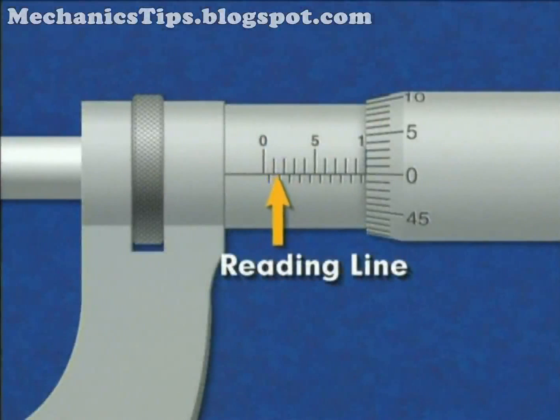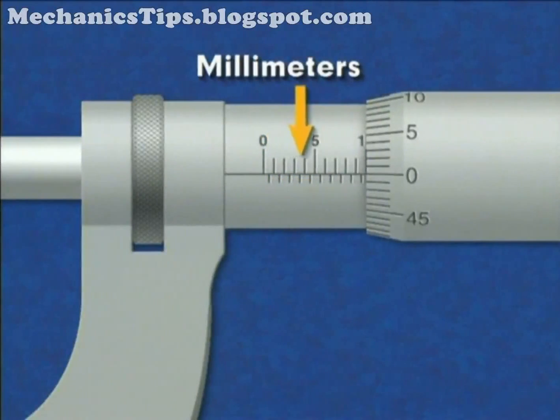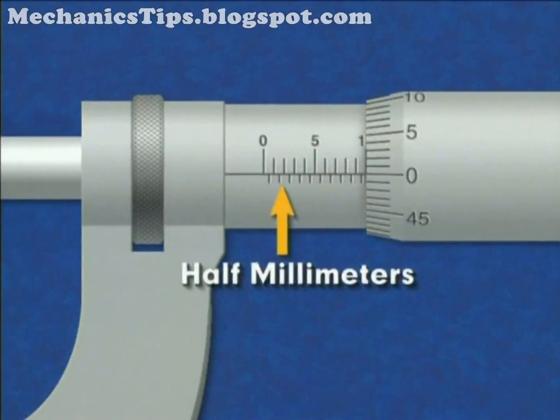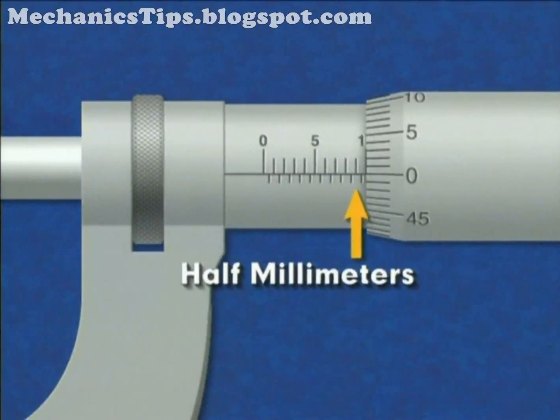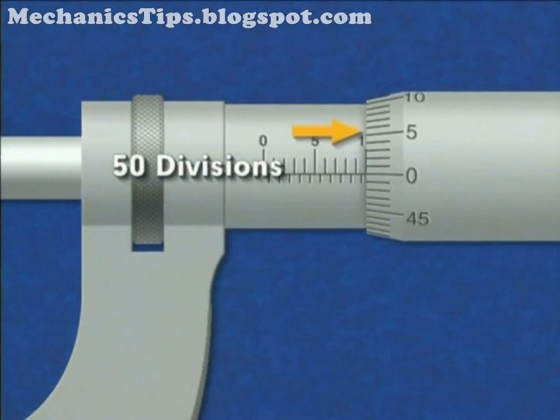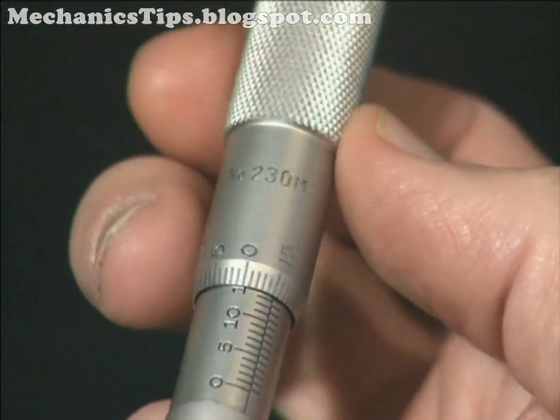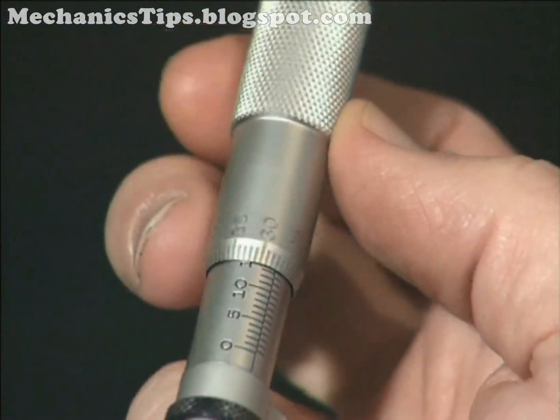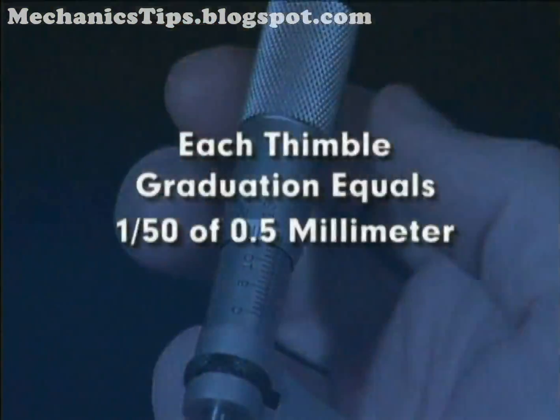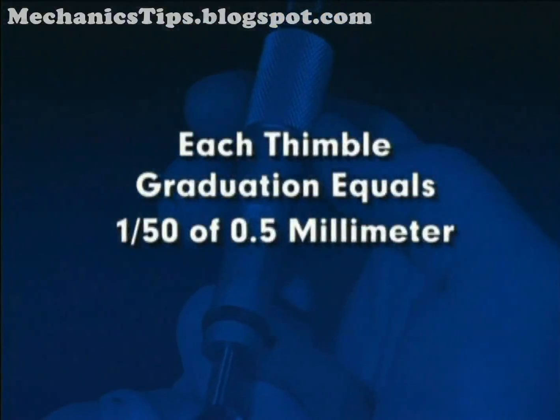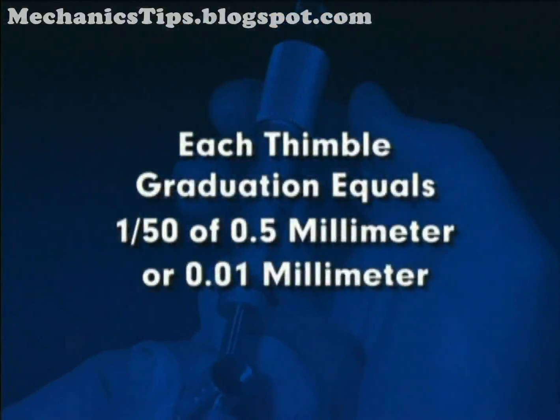The micrometer has a reading line on the sleeve. The vertical graduations on the top of the reading line each represent a single millimeter. The vertical graduations below the reading line indicate half millimeters. The beveled edge of the thimble is graduated into fifty divisions. Since a single revolution of the thimble moves the spindle one-half millimeter, each thimble graduation equals one-fiftieth of one-half millimeter, or one one-hundredth of a millimeter.